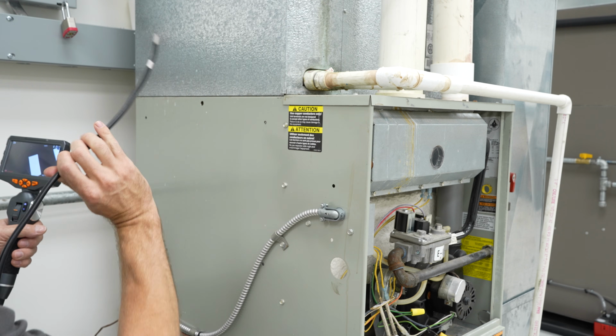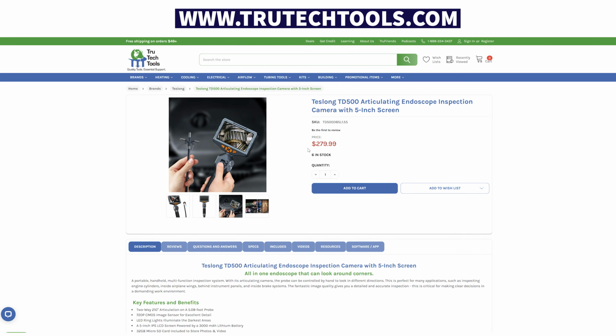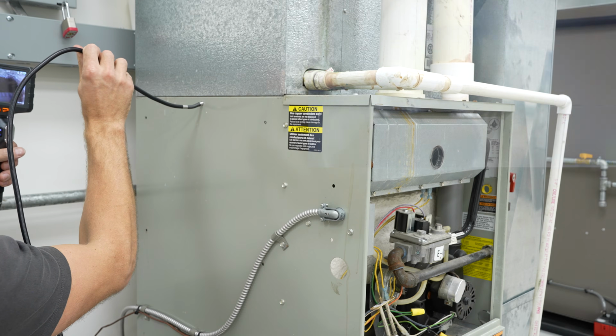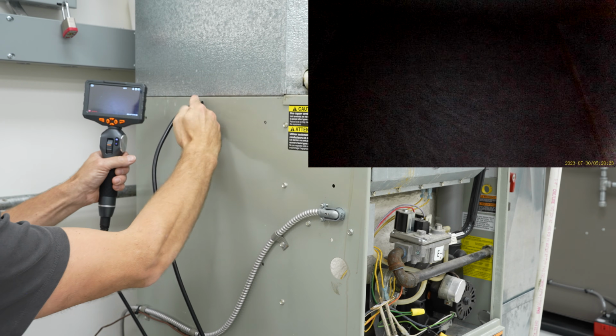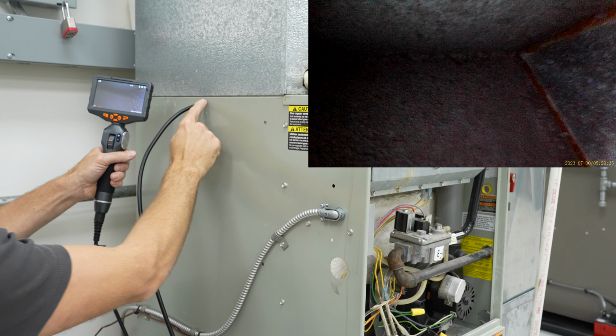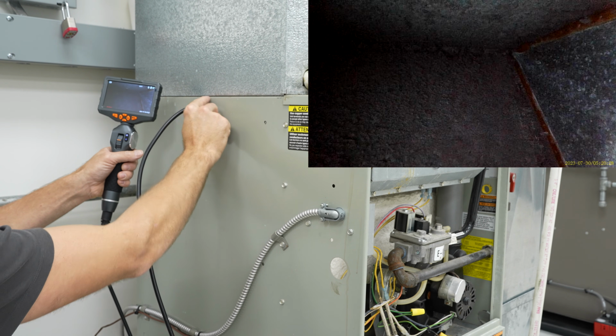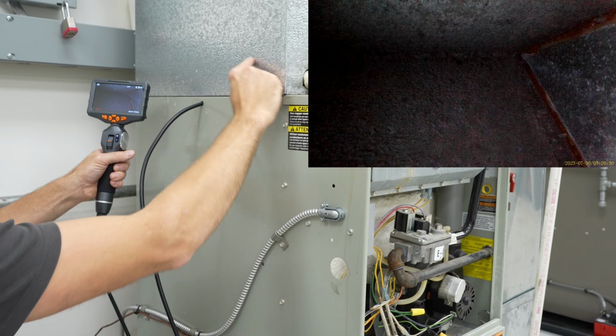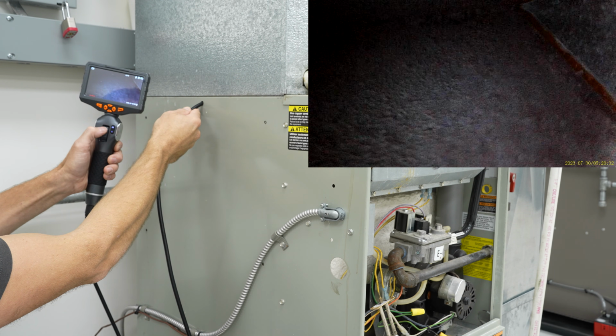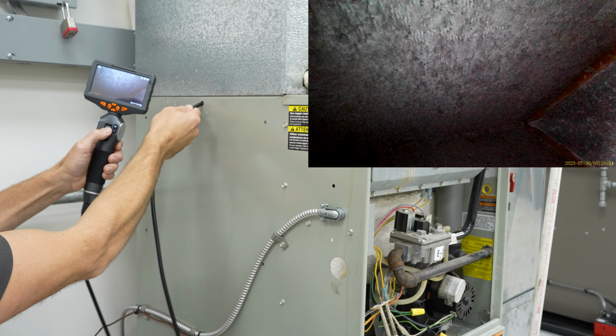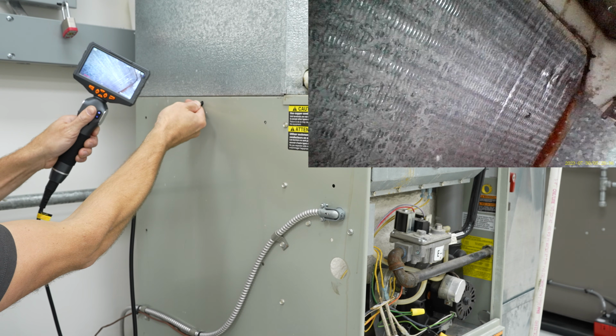And so this is a Teslong video scope. You could find this over at Trutechtools. You could also drill a hole into the side of the furnace here. You just want to make sure to do that with a unibit, and make sure to not hit the heat exchanger, make sure to not hit the refrigerant coil, and then you can go ahead and take a video of the entire inside of your evaporator coil here.